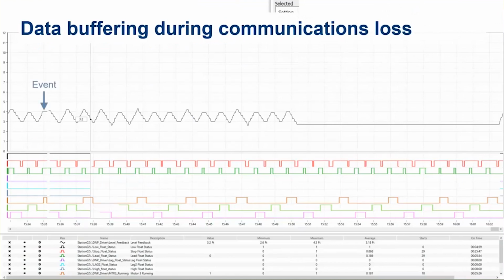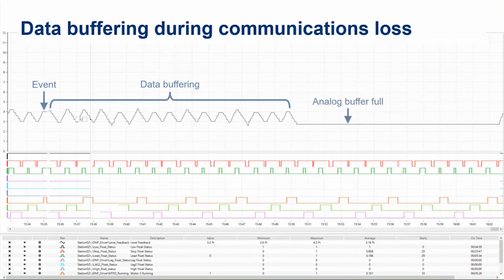So in this situation, we had an event. We lost communication at this point right here where it says event. During this time period, we buffered the controls at this station that was using a level transducer. And if you count those level transitions, we went through 12 cycles of the lift station pumping down and letting it fill back up, okay, before we ended up filling up our entire buffer. And of course, I'm doing this on a simulator to create a lot of activity. Next, what you'll see is the analog buffer is full, so it's not collecting any more data. And then this is where communication is restored, and it backfills in the SCADA system's information on the graph.